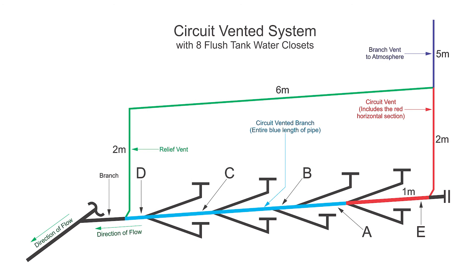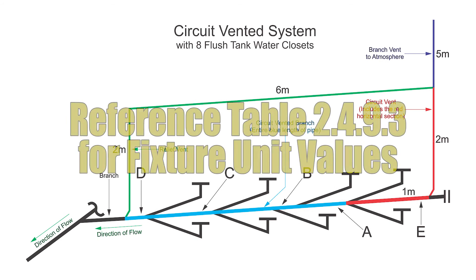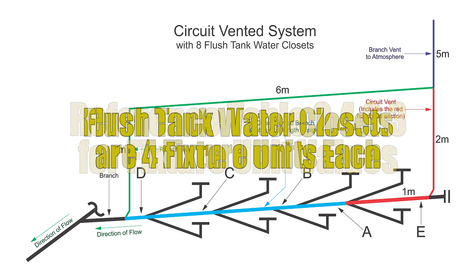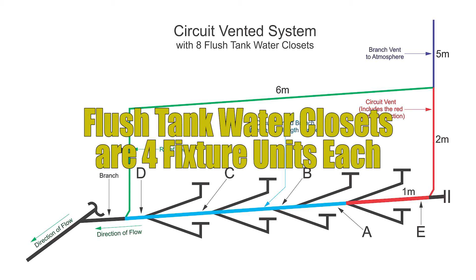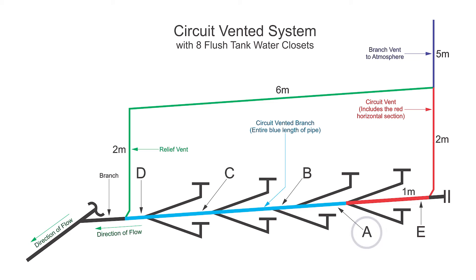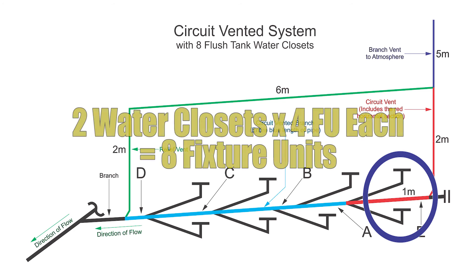So we're going to size the circuit vented branch. You'll need to reference code table 2-4-9-3 to find the fixture units of the different fixtures, but we have flush tank water closets — they are 4 fixture units each. Pipe A has 2 water closets draining through it, so 2 times 4 fixture units equals 8 fixture units.